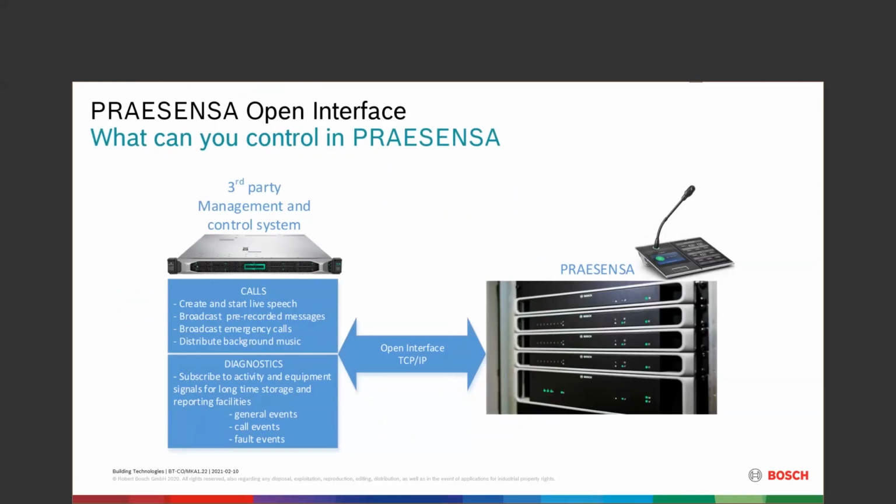So all the calls which you can normally control through contacts or through the call station from PRAESENSA, you can also manage through this open interface. The diagnostics is done also there by subscriptions to events, for example, that you can get all the general events of all the call events, all the fault events from your system. So you can really subscribe to the particular objects in the PRAESENSA system if you need to have diagnostics information about this.